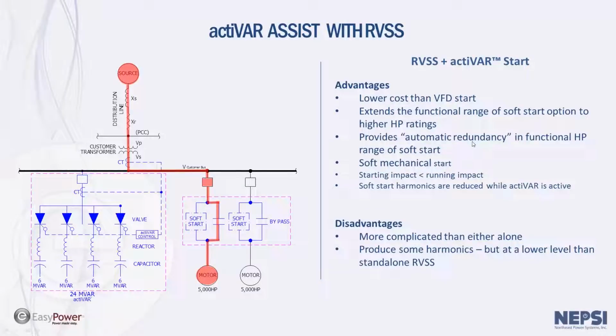In addition to saving money, the actiVAR could also provide automatic redundancy for the system. So the actiVAR can be sized to start the motor and meet the voltage sag limits of the utility. It would serve as a backup for the soft start, and we can also get that soft mechanical start that we discussed earlier with the soft start, that the actiVAR cannot do alone.